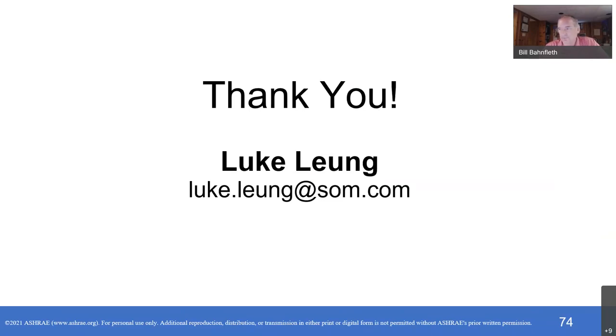Bill, while I've got you on the camera, next one's for you. So the question is, what is the basis for the Harvard Colorado 5-6 air changes per hour recommendation? I hope I articulated that properly. That's an important question, because that recommendation is so widely circulated. And actually, if you get Joe Allen's article that he co-authored on air changes fairly recently, what it says is, well, 5 to 6 air changes per hour is in the range of equivalent air changes that we see in healthcare facilities. So it's explicitly not a COVID risk assessment based number, but it is, I think, appropriate given what we know about healthcare infection control.